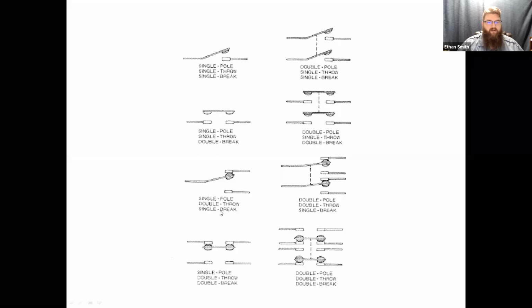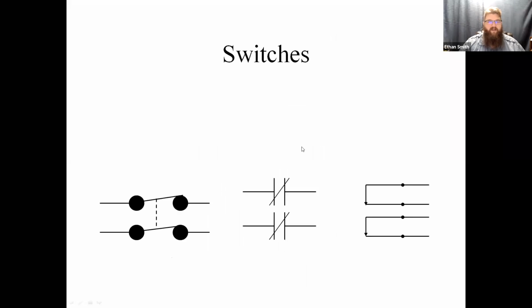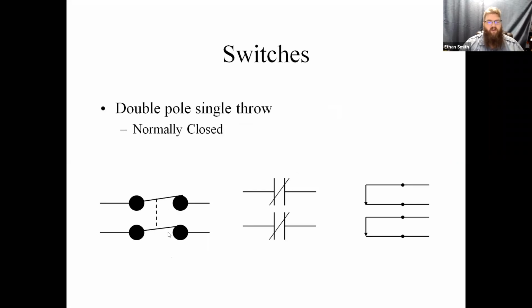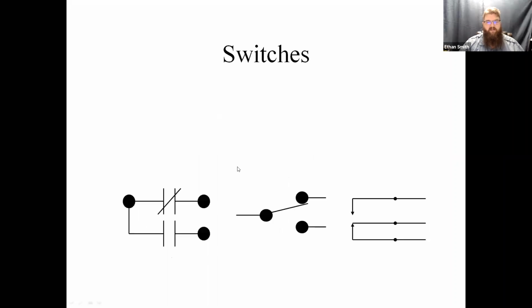After that, we can get into double throws. So this would be a single pole double throw because it has two closed positions. So this one is either normally open down here and normally closed up here, or normally closed down here and normally open up here. We can do that as a double break solution as well. We can go into double pole, single throw, single break, double pole, single throw, double break, double pole, double throw, where we have two closed positions, single break, or we could go all the way up to double pole, double throw, double break. So they just get more complicated as we go up. So this would be your double pole, single throw, normally closed, because its unenergized position is in that closed state.